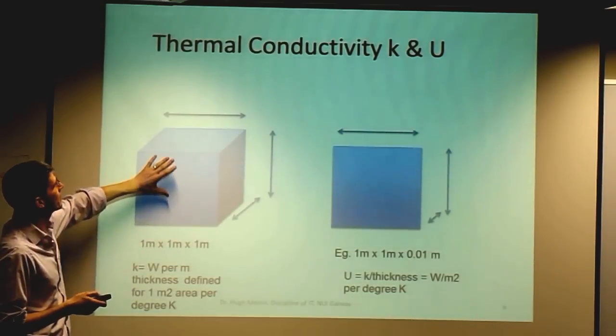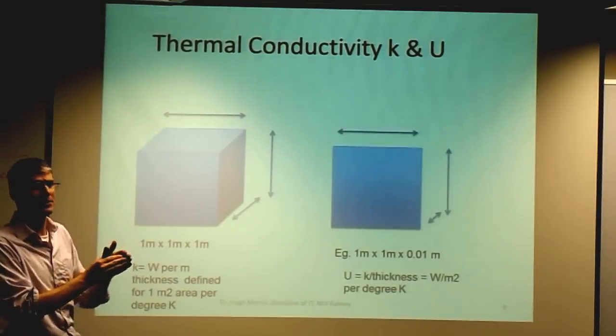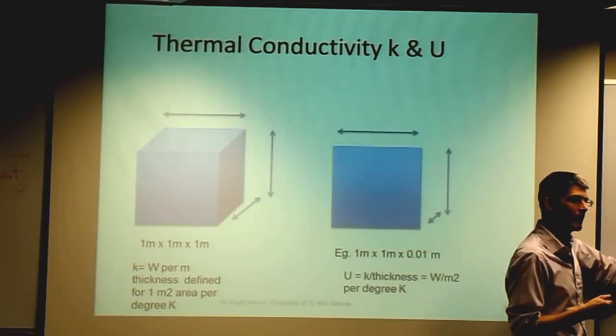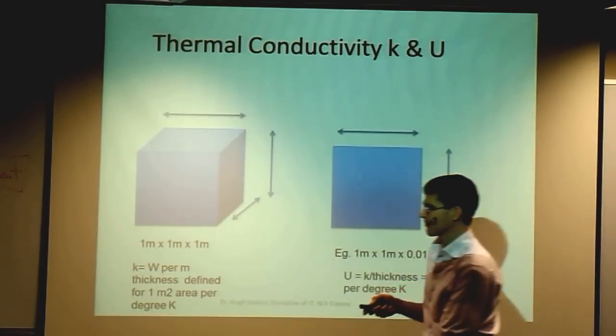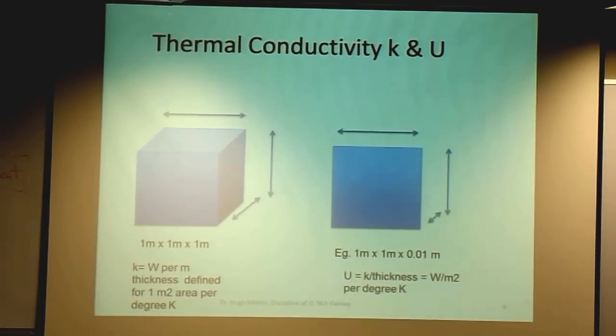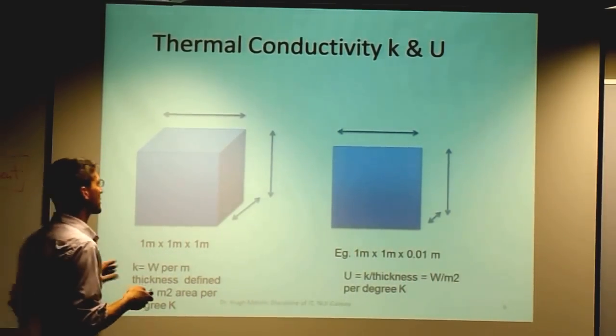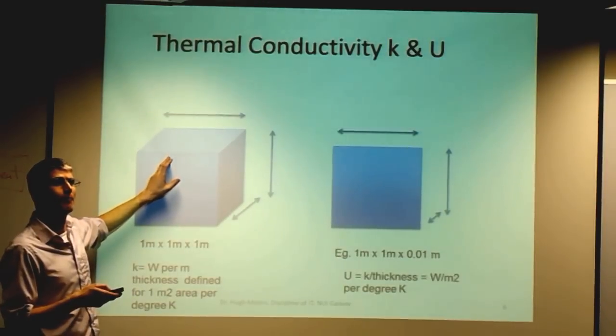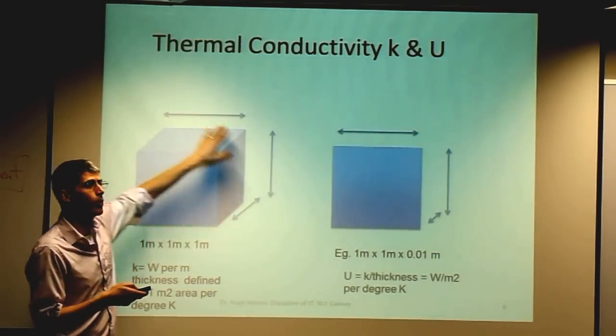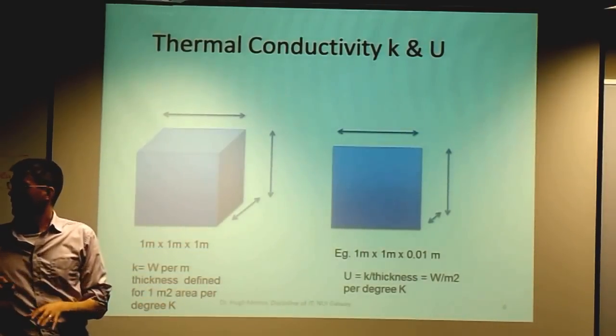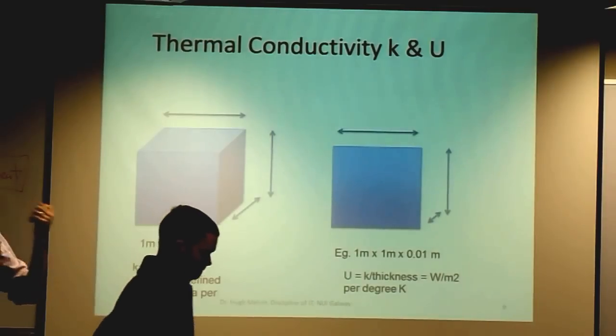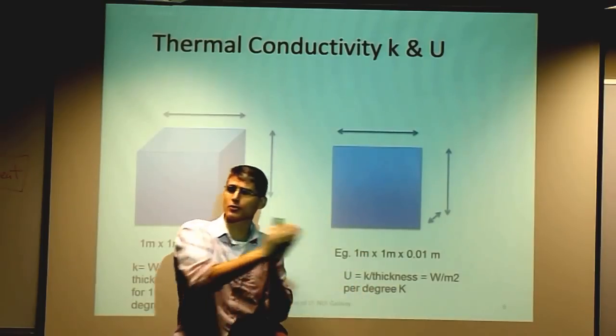The main difference between them is that conductivity is defined for a block of material that's a meter thick, whereas the U-value is defined for a structure that might be x millimeters or x centimeters thick. Thickness really is the only distinguishing feature between them. Otherwise they describe the amount of energy in terms of joules that transfer per unit time, per second, per meter squared area, for every temperature degree differential. How quickly will energy flow from hot to cold? That's essentially what the U-value or conductivity means.